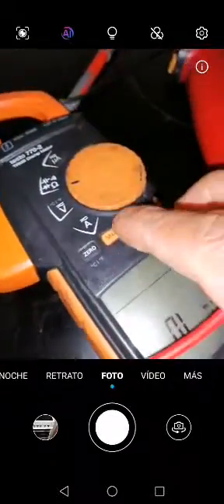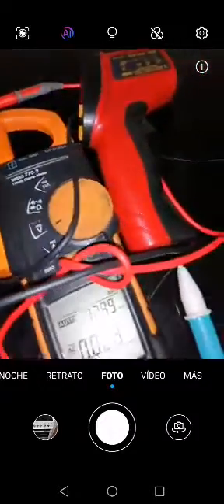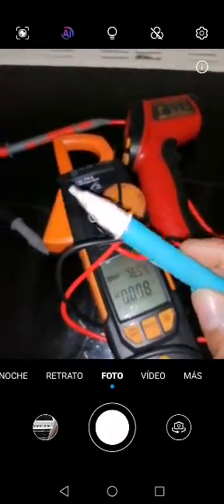In order to fix this problem, what I did is I turned the power off. I got my multimeter out, then I checked my multimeter — the multimeter is working and my volt stick has a backup. Then I went to the back where the power is, put it on voltage, and checked my live and neutral to look for safe isolation, and then as a backup used my volt stick.